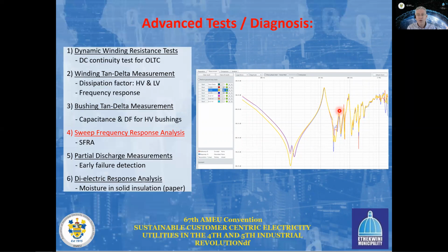So it means we want to compare this measurement against a measurement from either when it left the factory or from before it was commissioned and so forth. And this comparative measurement then gives us a conclusion whether something has changed inside this transformer. So it's important to remember that this is a comparative measurement and not an absolute measurement where we have a certain pass or fail criterion available.